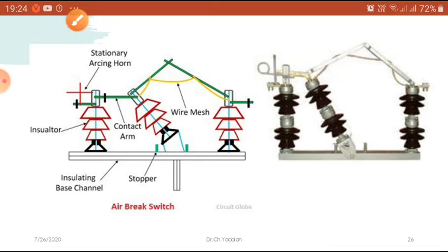While it is going slowly in this direction, the arc also develops and spreads more and more. Once it spreads, it contacts the air present nearby, and automatically whatever heat is present in the arc is absorbed by the natural air. Once the arc collapses due to the loss of its temperature, it cannot sustain further arcing.